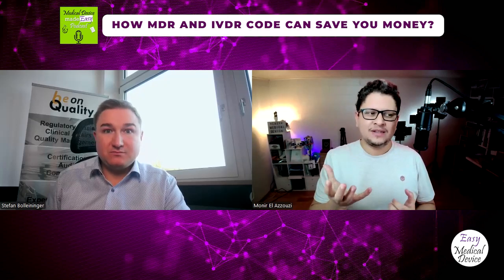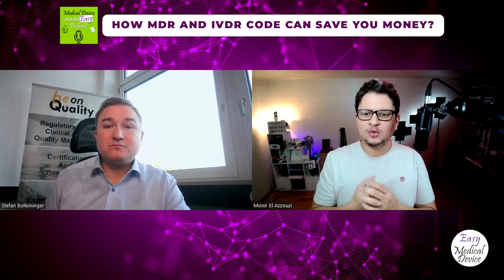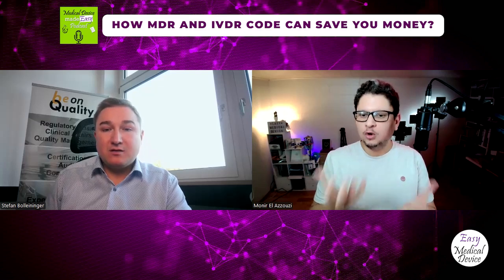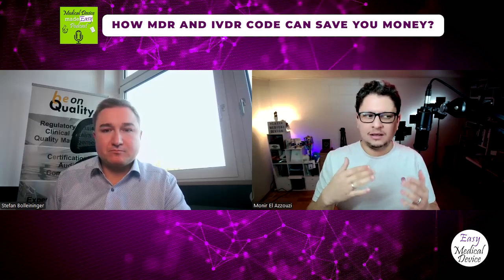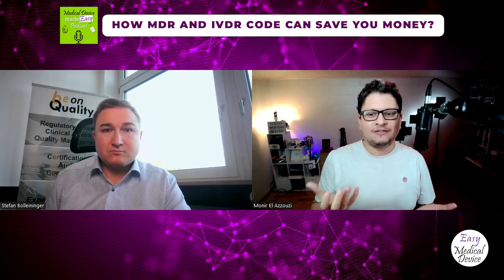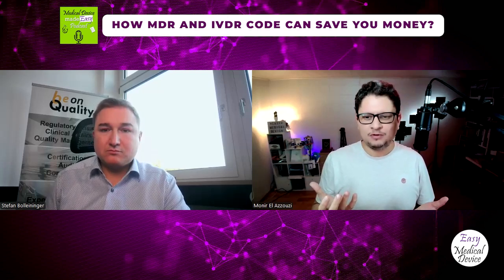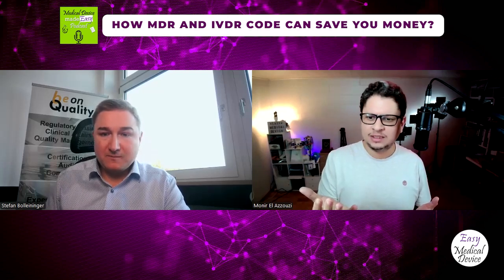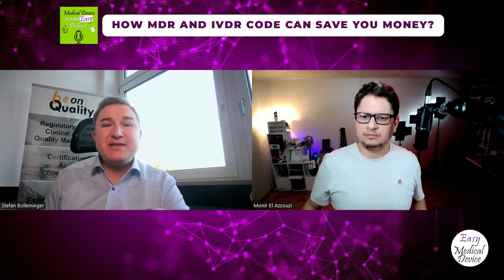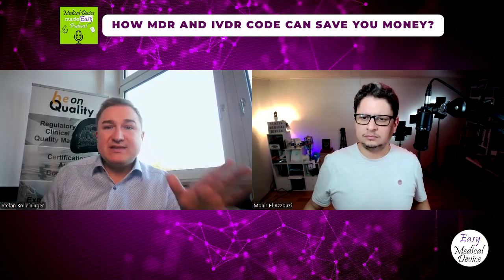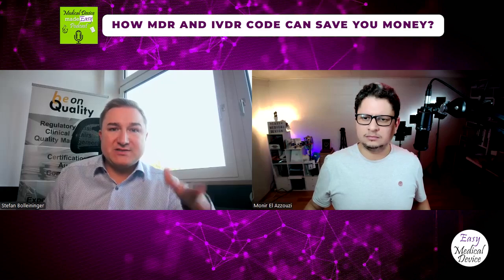So you said that the notified body will use that to select an auditor mainly. Correct. So meaning that I suppose they already have an auditor available for this type of code. I mean, otherwise you cannot select this notified body. Correct. For the MDA and MDN codes, yes, because all the notified bodies are scoped based on those codes as well. So when you go to the Nando database, you can see whether my notified body can do my products. And that's important for adding new products or what your long-term strategy and long-term goal will be.